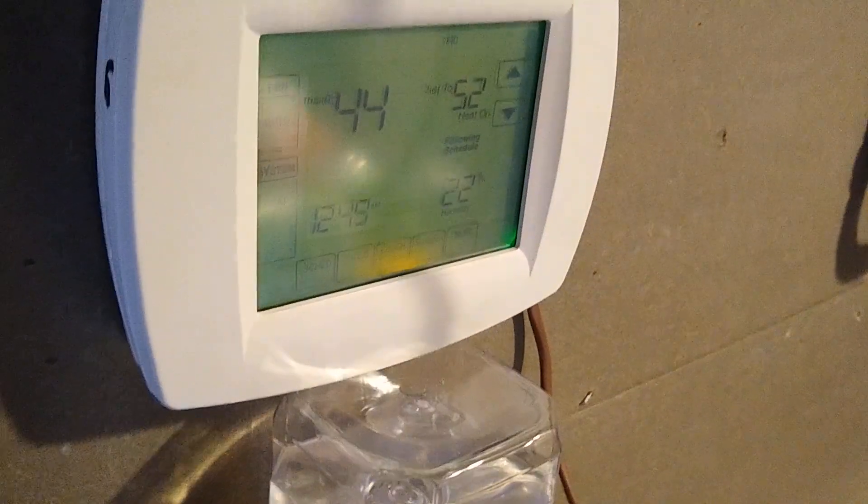And there we go. Thermostat just called for heat. Heat on. You can hear the fan going. If we're lucky this thing will work fine. So I believe that fast blink is just normal operation mode when it is calling for heat, and we should expect ignition in just a second here.